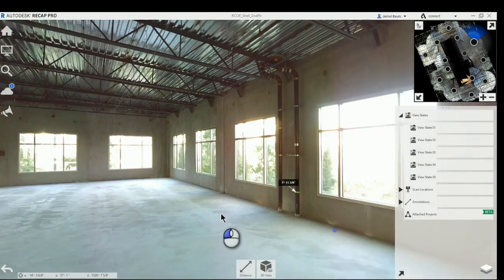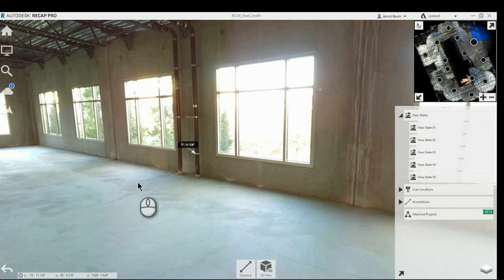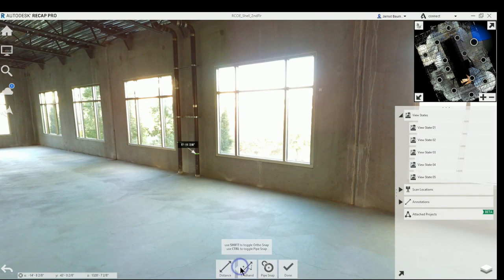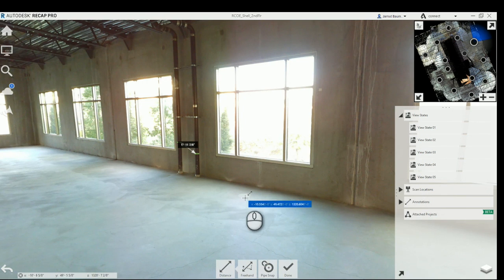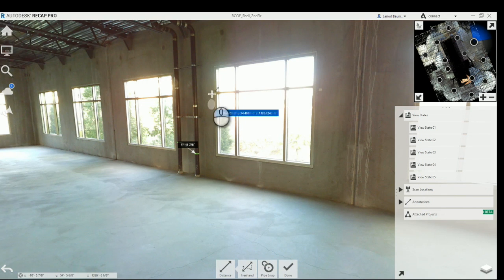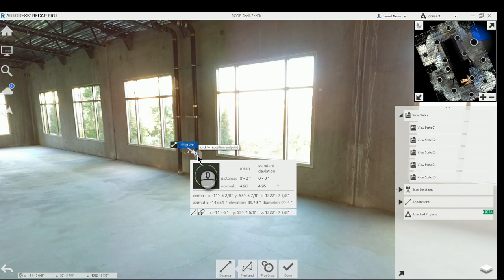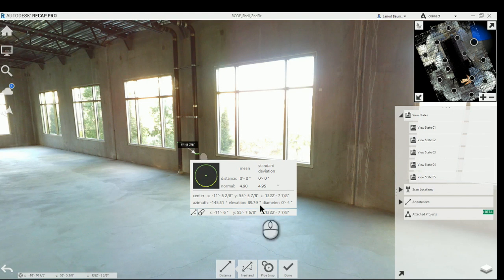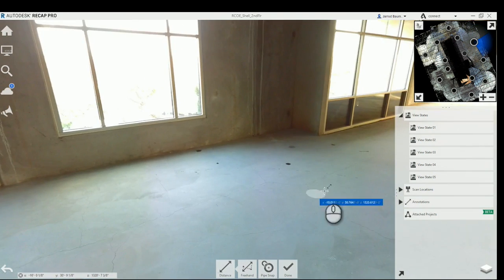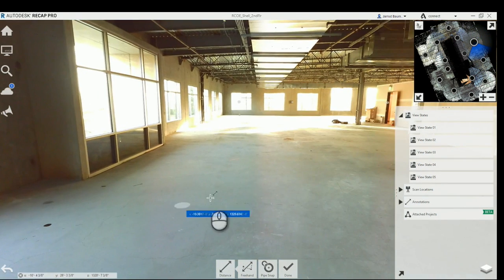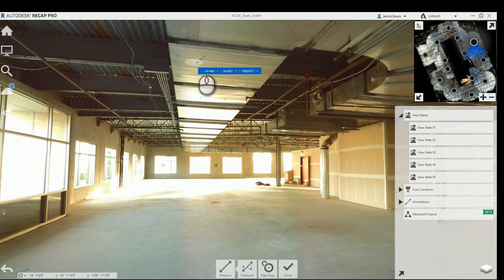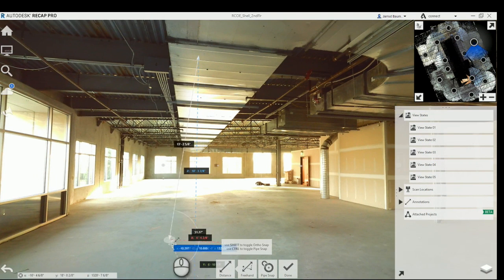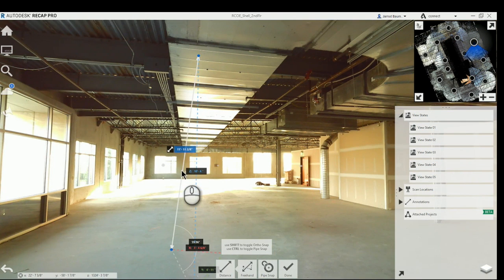Very beneficial for design teams, architects, and engineers as they design a space where they might have to make multiple trips to the site to get information. As you can see, these are fully able to be dimensioned because these photos are linked to the 3D measurements. You can see I can get pipe diameters here from existing piping. We can also measure finished floor elevations of ductwork above the ceiling.